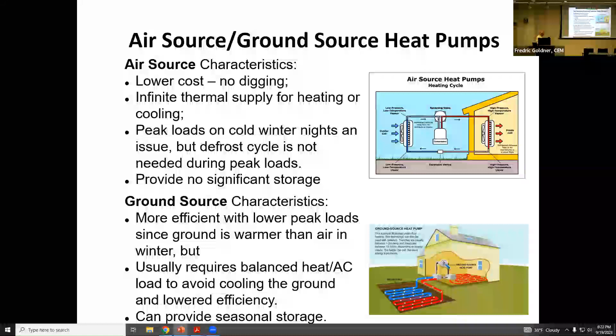Ground source systems are more efficient in that they need less electricity. They have higher COPs averaged over the year because the heat is coming out of the ground and the heat there is more like 50 degrees or 55. Come back in a couple of slides to the issue of balance, but you do have to pull comparable amounts of heat out in the winter to what you put down in the summer or do something about it. And because you're using the ground as the place to store heat, you can actually get seasonal storage at a reasonable price.